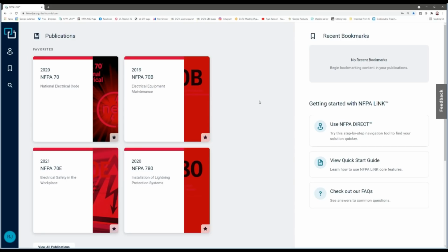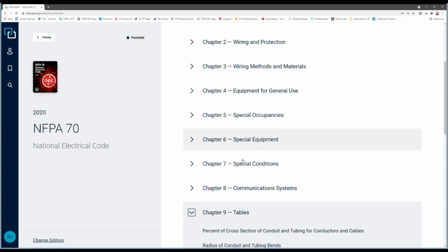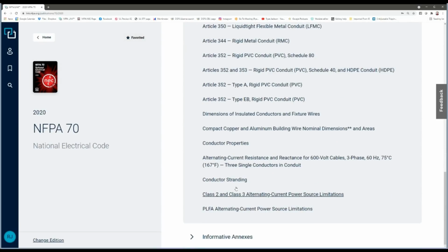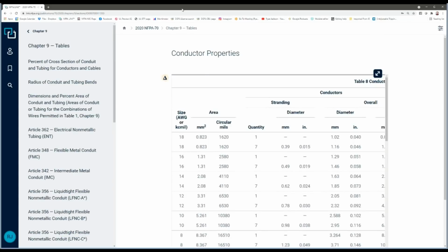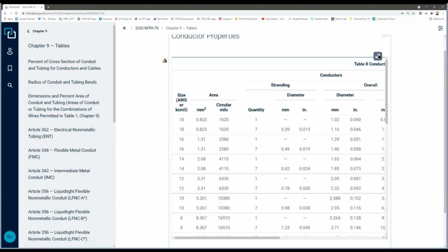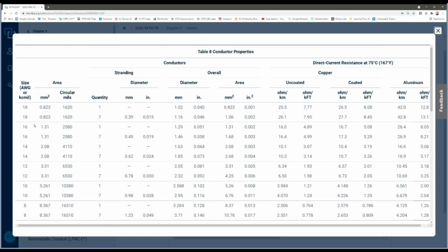All right, let's go ahead and open the code book for a second. I went to my NFPA link page. That's the digital version of the code book. And I'm here under the 2020 NEC. We're going to click on that, open it up, go down to Chapter 9, which is the tables. Table 8 is down here at the bottom. It's conductor properties. And that's where I'm going to find the circular mil area for my conductors. All right, so if I want to make this a little bit bigger, you can see that on the left, I've got the size of my conductors in American wire gauge or circular mil. I go down here to 12 gauge, and I figure out that the circular mil of a 12 gauge is 6,530. So I'm going to write that number down because that was my starting point.